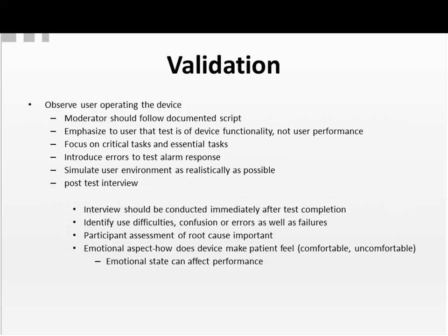The validation is observing the user operating the device. The moderator should follow a documented script. It's important to get a true validation. You emphasize to the user that the test is of device functionality, not the user performance. You want the participant to be relaxed, not to think that he is being judged. It's a test of the device.